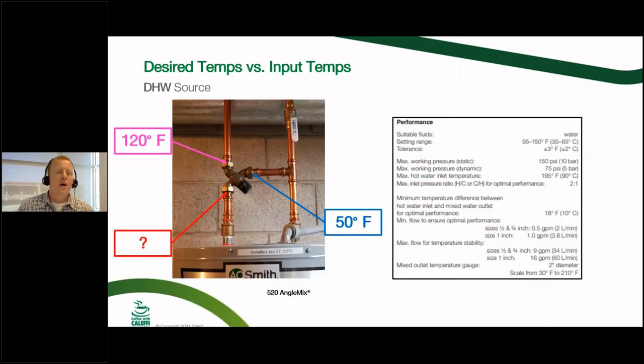All right, now the next one that comes up is temperatures, inlet, outlet. Why is it working? Why is it not working? And things like that. So, just for round numbers, say you want 120 degrees to come out of a mixing valve. Every mixing valve is going to have a minimum temperature difference between the hot inlet and the mixed outlet for optimal performance, is how we note it there.